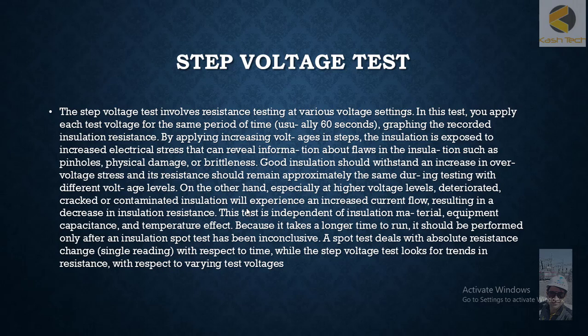A spot test deals with absolute resistance change — a single reading with respect to time — while the step voltage test looks for trends in resistance with respect to varying test voltages. If you are doing the spot test and not getting a satisfactory reading, or the reading is not stable or is coming out low, the next method to check further and get conclusive proof is to do the step voltage test.